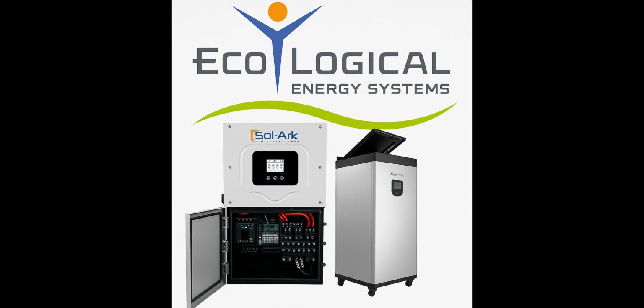And the time of use mode sounds like it offers a lot of flexibility. Absolutely. Time of use, TOU mode, gives you the ability to create a schedule for when your battery charges, discharges, and when you might sell power back to the grid, all based on specific time slots. For those tiered rates. Exactly. This is really useful if your electricity provider has different rates depending on the time of day. When you're setting up TOU mode, you need to carefully configure the permissions for charging in the battery settings. Grid charge, generator charge. Right. You can choose to allow charging from the grid, a generator, or both, and then define the target battery percentage or voltage in the TOU table for each time slot. Set the target for each period.